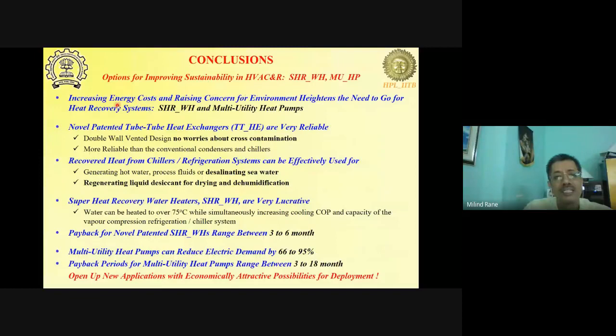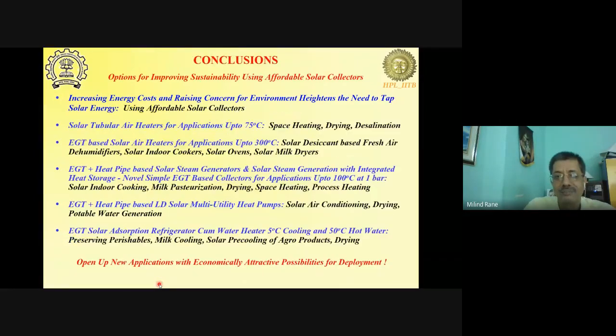Okay. And on the other hand, you have superheat recovery and heat pumps. As I said, most of the time paybacks can be 6 months or lower for superheat recovery. And for multi-utility heat pumps, it can be typically less than a year. Okay. So 3 to 6 months for superheat recovery and 3 to 18 months, depending on how many hours you're using it and things like that. So basically, our technologies are opening up economically attractive applications, and then using affordable solar collectors, we can use it for space heating, drying, desalination. We can use it for high temperature applications like milk dryers and so on, liquid desiccant fresh air dehumidification, solar cookers, solar ovens, and so on and so forth.